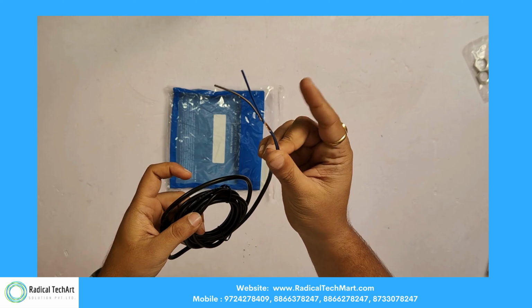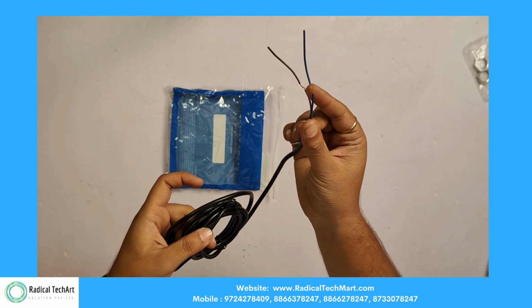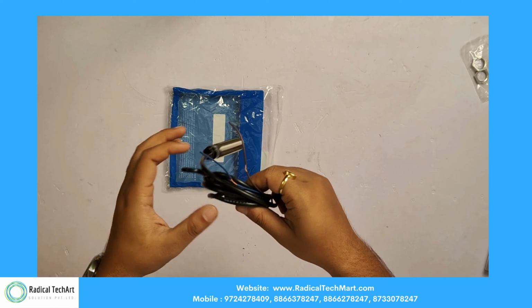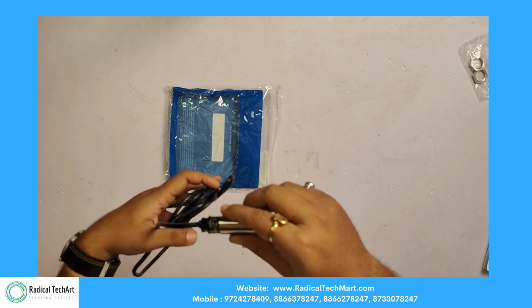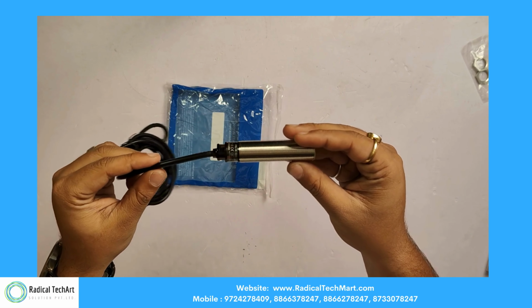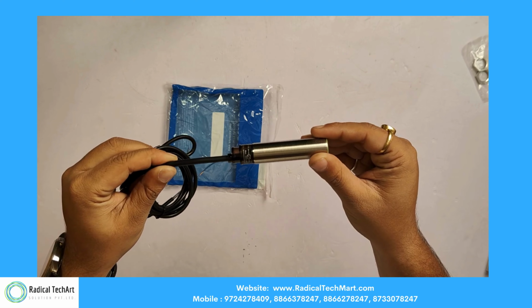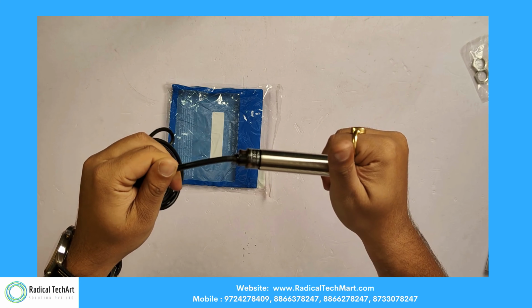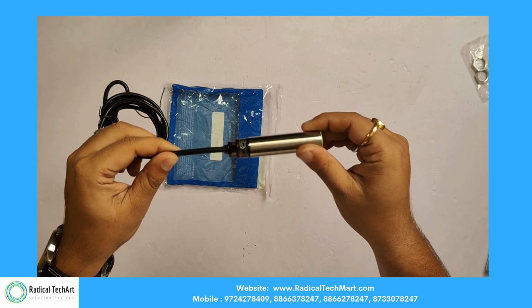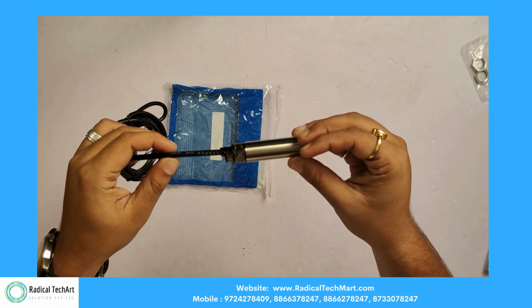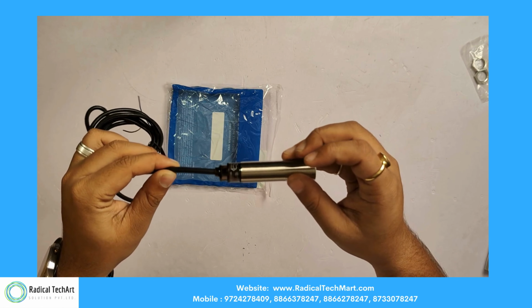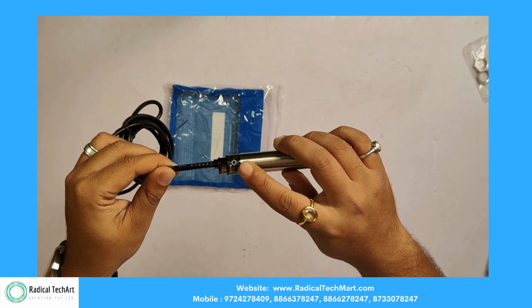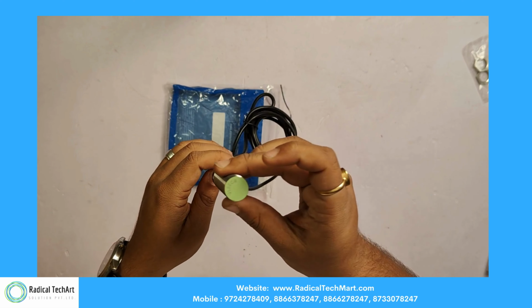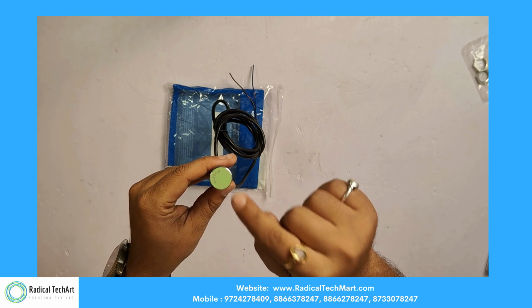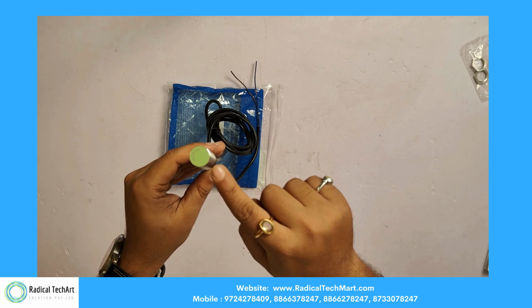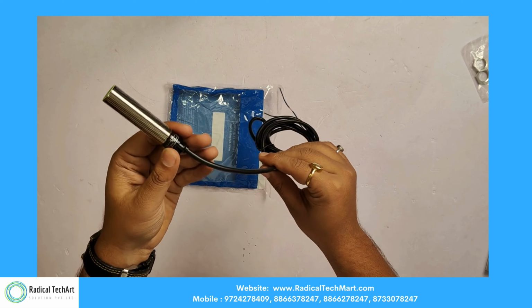Here is the main 2-wire for the connection in the series. Sensors are versatile and can be used with a wide range of materials and object types. So, here is the sensor housing with the sensor end bell. And on the top, we have an indication light for better understanding. And on top, we get the sensing face, which has a green color, and it works as the electromagnetic field created by the sensor emanates from here.